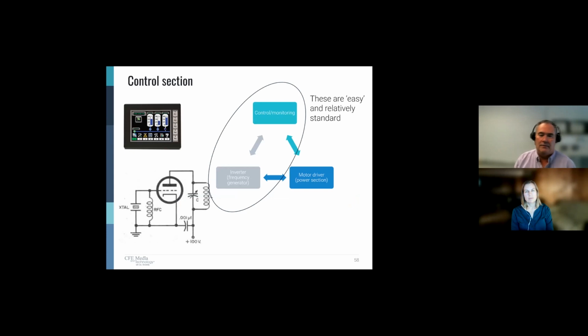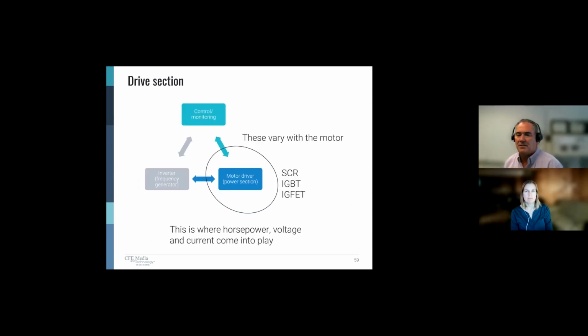Some things to keep in mind: the first two boxes in this graph are relatively easy and relatively standard. It's fairly small components, very easy to do, typical solid state stuff, not a big deal, fairly inexpensive. Where it gets expensive is on this backside. These vary with the motor, and this is where the horsepower and the voltage come into play. There's three or so different technologies that you'll see when you talk about big VFDs. SCR, silicon controlled rectifiers, insulated gate bipolar transistors, and insulated gate field effect transistors will all be used for these large driver sections. More than you probably wanted to know, but there it is.